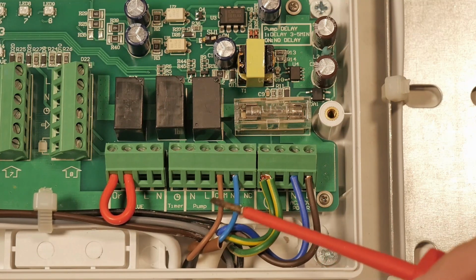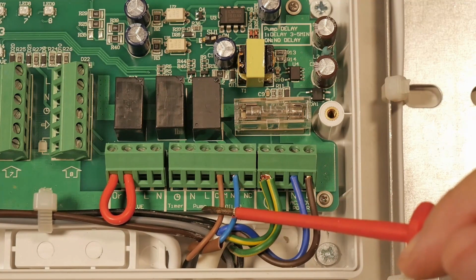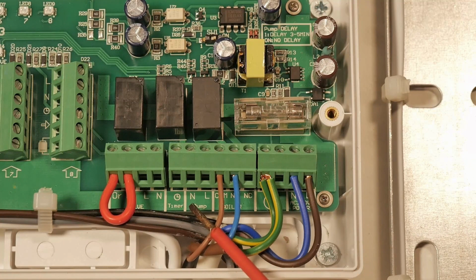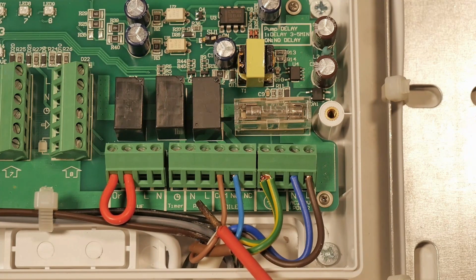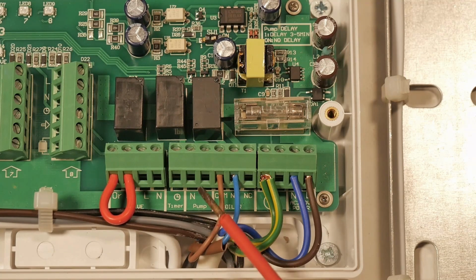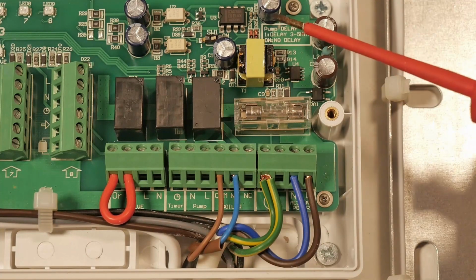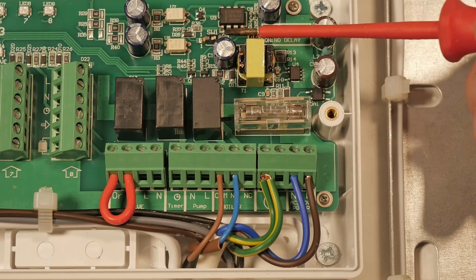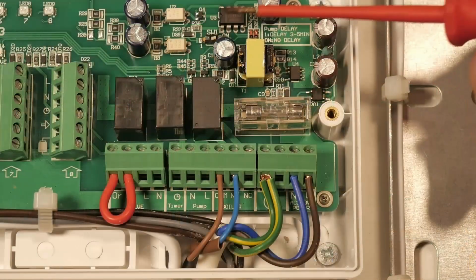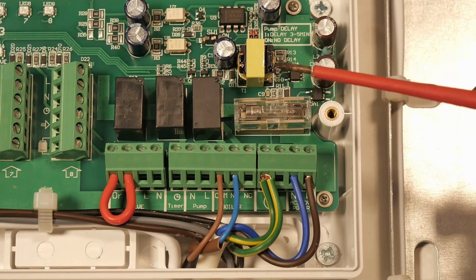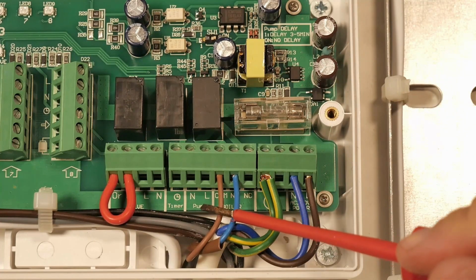It's quite handy that the volt free is already included in this. You've got the pump live, pump feed out for your localized pump. This would be a pump that's on, say, a manifold, or perhaps the localized pump back at your low loss header that relates to this manifold, so you'd be wiring your pump from there. Up here we've got a timer delay for pumps, so if you wish to have pump delay on, click this over to off, and it is then pump demand delay on. Weirdly, it is back to front on that.